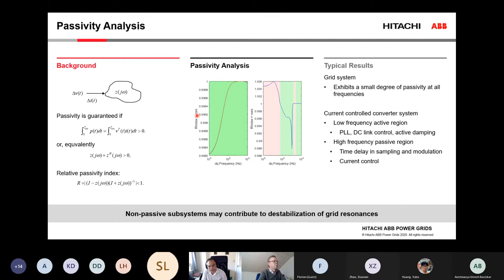For a converter system, the picture often looks like this. So for low frequencies, we have an active region up to some frequency here. And then you have some passive region, and then the non-passive behavior comes back at high frequency. So this non-passive region at low frequencies is basically dictated by our requirements. We have a lot of requirements in terms of how the converter system should respond to voltage disturbances on the grid. We should be able to ride through faults and things like this. So it actually forces us to make the control have a certain amount of performance that allows us to meet grid code requirements. And that basically implies we also need to be non-passive.